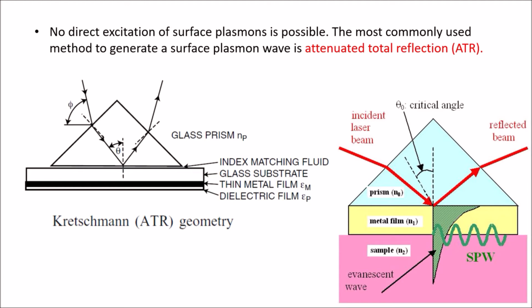Upon total reflection of the incident light at the interface where the prism touches the metal film, a small fraction of the light extends into the metal film as an evanescent wave, which even extends into the sample as this metal film is very thin. At a certain angle, the electromagnetic wave couples to the interface as surface plasmon. This surface plasmon excitation attenuates the reflected light, and this drop in intensity of the reflected light is shown here.